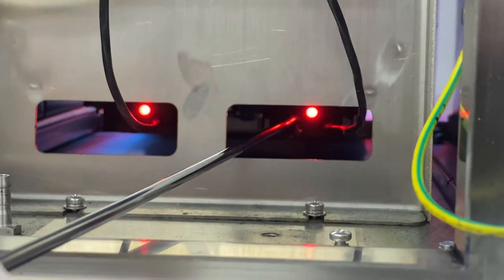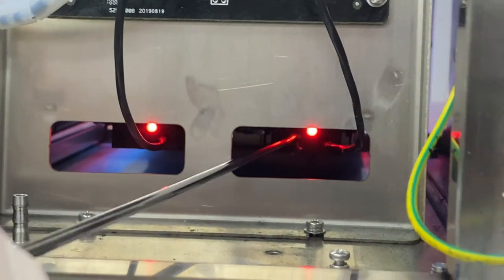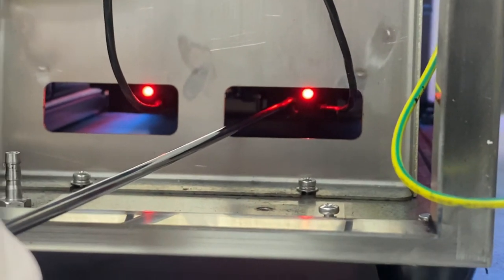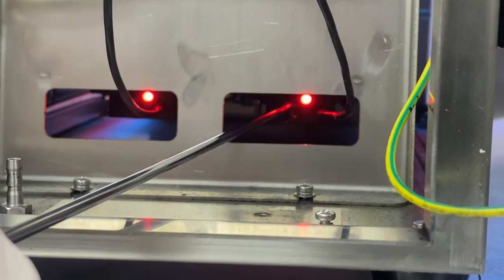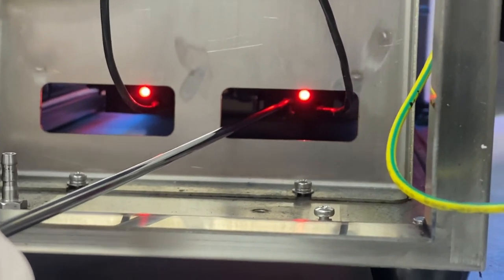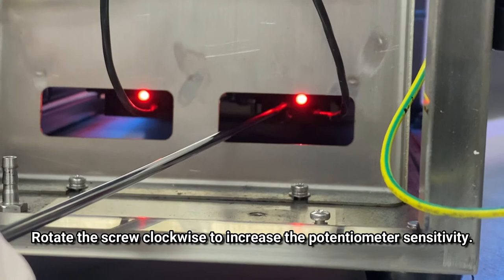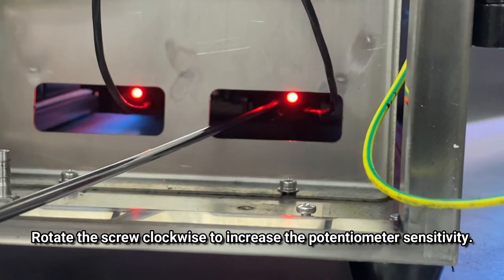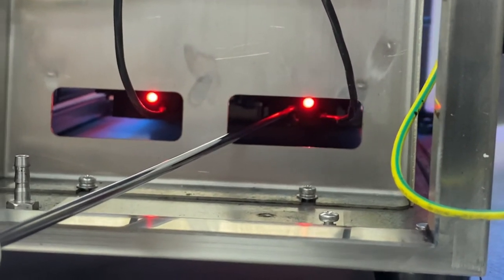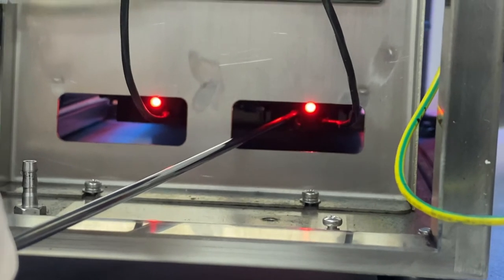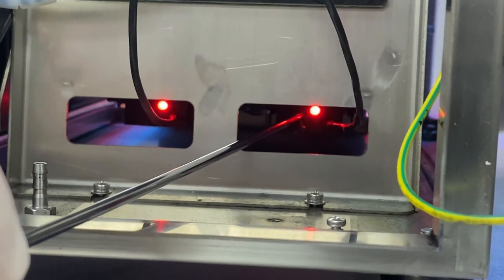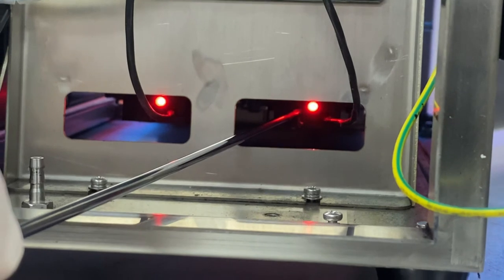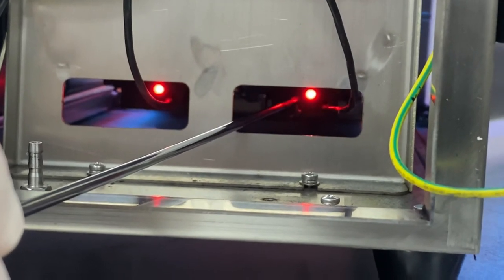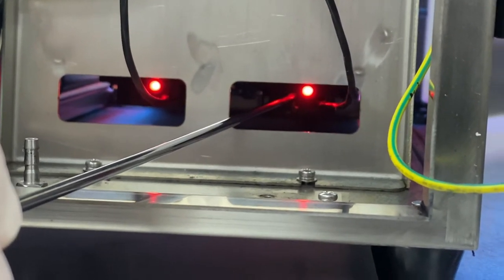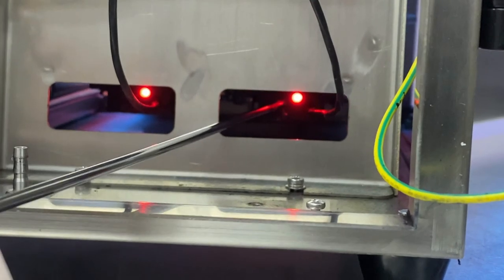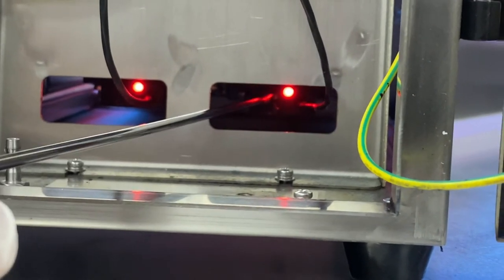All we really need to do, if by chance we have a cartridge with fluid installed and the light is not on, is rotate that potentiometer clockwise, which will increase the sensitivity. Rotate it until the light turns on. If by chance this light is always on, even with an empty cartridge, you can rotate the potentiometer counterclockwise to decrease the sensitivity. So fairly straightforward how to adjust this.